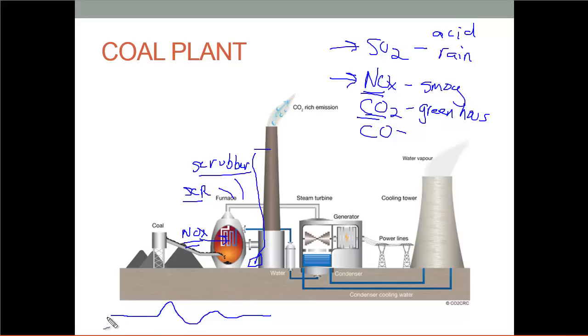But that's one of the things that happens: you talk about the swing rate of the unit. A lot of times maybe these things can go up or down plus or minus, say, 12 megawatts a minute or something like that. 12 megawatts would be pretty high. Maybe 5 megawatts a minute. It just depends on the unit and what the unit's capable of doing. But these things can only swing so much. Okay, so if you've got 2 units here, maybe you can swing 10 megawatts plus or minus a minute.